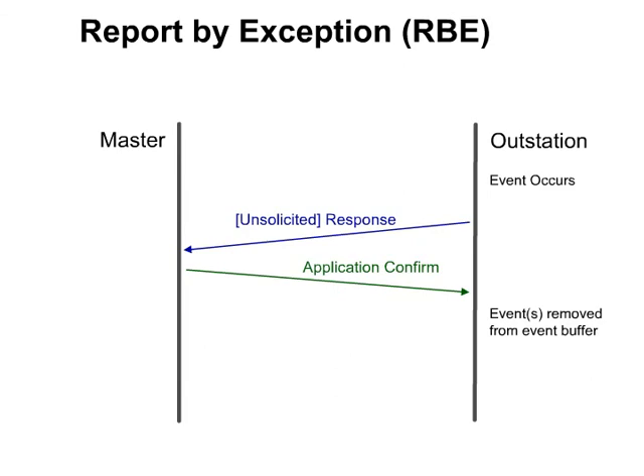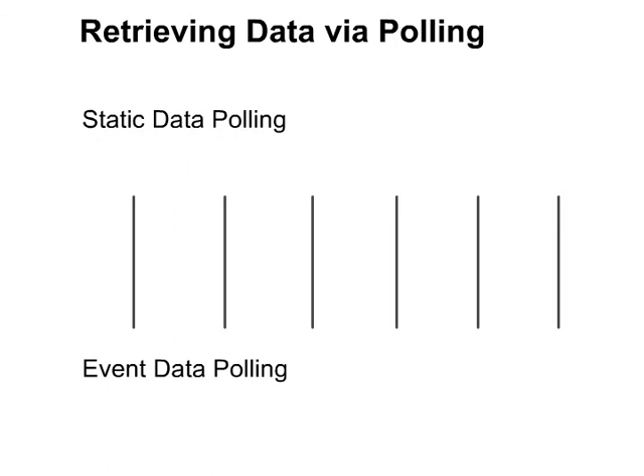Let's take a look at the difference between static data polling and event data polling using a digital input as an example. The master polls at a specified interval, indicated by vertical black lines. At the start, the input is low. The input then transitions to a high state. Whether the master polls for static data or event data, the device will report the high state on the next poll. However, with DNP event data, the outstation could also report the time of the transition. Next, the input transitions low and then high again. With static polling, this transition is missed as the device reports the current state on the next poll. With event polling, however, the device reports both transitions.